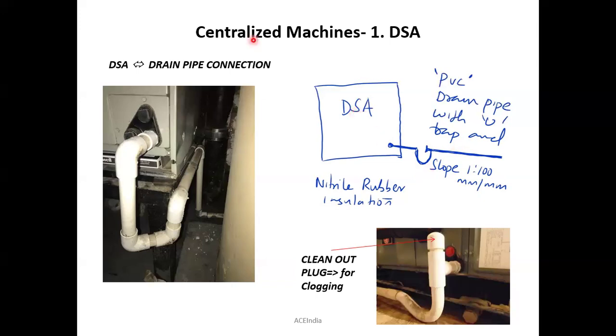Is it like an NRV? Not like an NRV. NRV means non-return valve. The U-trap is preferred. In the U-trap, some kind of trap seal will be there. Trap seal means some kind of effluent, that is the water. The water should be kept at the bottom of this U connection itself. A little bit of water will be there, so this water will hinder the flow of any kind of odors into the machines.